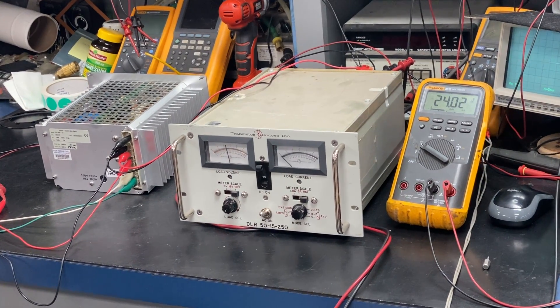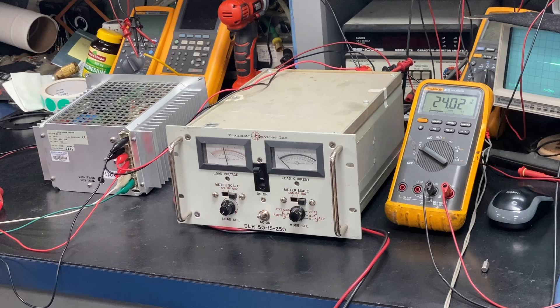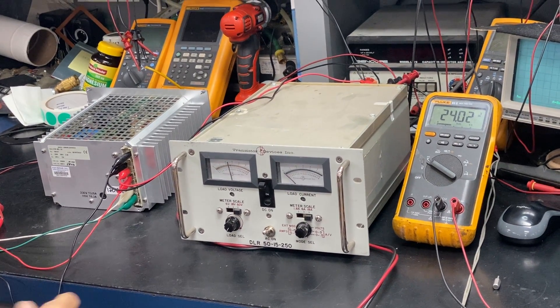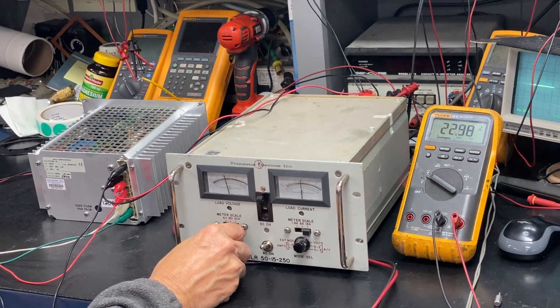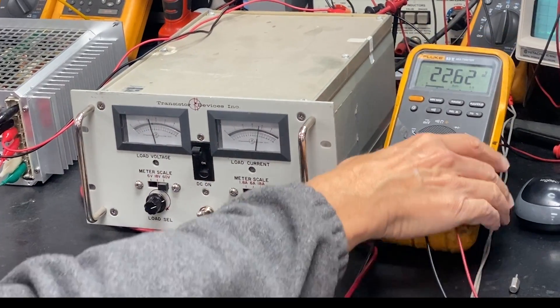Hello, today we are doing a final test on a power supply that needs repair and service. The first thing we'll do is hook it up to load. This particular device is rated at 24 volts or 12 amps. So what we want to do next is to increase the load current to approximately 12 amps, which we've done. And you can see here on the meter, we're at 22.51.